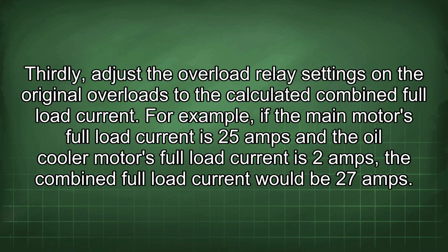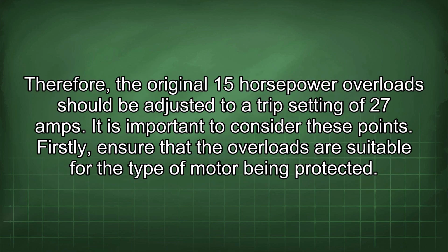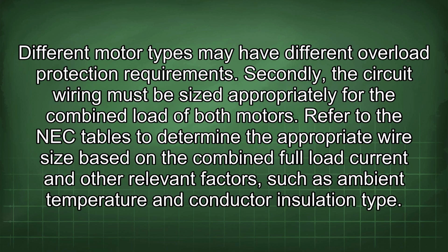For example, if the main motor's full load current is 25 amps and the oil cooler motor's full load current is 2 amps, the combined full load current would be 27 amps. Therefore, the original 15 horsepower overloads should be adjusted to a trip setting of 27 amps. It is important to consider these points. Firstly, ensure that the overloads are suitable for the type of motor being protected. Different motor types may have different overload protection requirements.